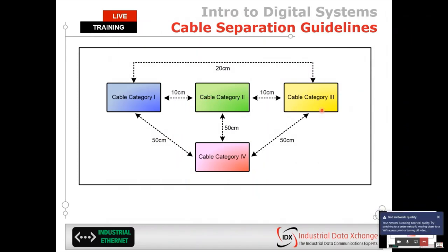Cable category three is anything above 400 volts AC or DC, and this should be at least 20 centimeters away from your industrial Ethernet cable. Category four is anything that has a risk of a lightning strike—such as a power cable going up to a lighting post in the field, or a cable running between buildings. This should be at least 50 centimeters separated from all of your cable categories.